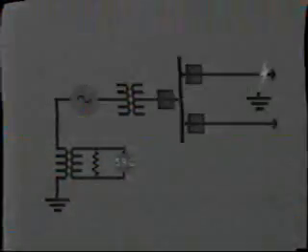This relay will operate for ground faults occurring in the generator, the primary of the unit step-up transformer, the primary of the unit station service transformer, and the interconnections. As previously discussed, a ground fault on the system would not normally be felt in the generator circuit. However, in certain situations, a ground fault may be felt due to capacitive coupling of the unit transformer windings. Therefore, operation of the sensitive 59G relay must be delayed to permit the fault to be cleared by primary protection on the transmission system.